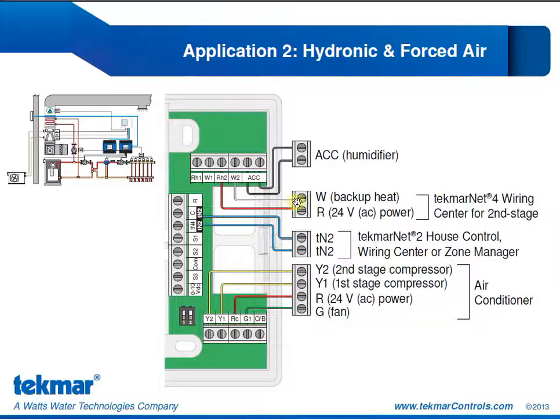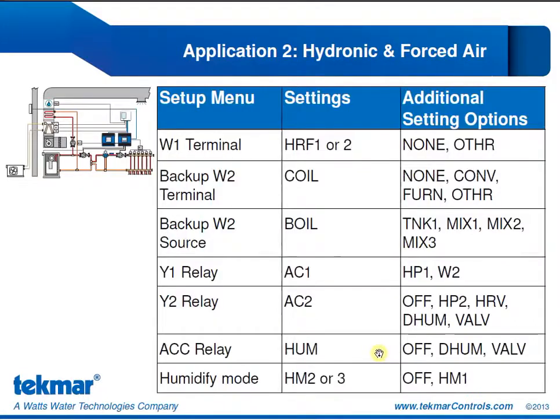Our second stage of heat will require us to bring the RH2 and W2 over to a tekmarNet 4 wiring center. So that will go to the W and the R for zone 1 on a tekmarNet 4 wiring center. We have the humidifier being controlled through the accessory relay, and we have our connections to the air conditioner. Power coming in, our Y1 and our Y2 connections for each stage of compressor, and the fan, of course.